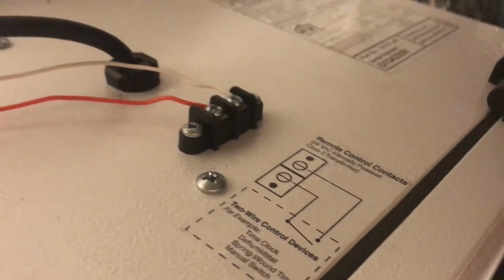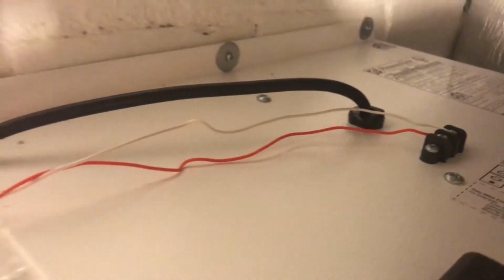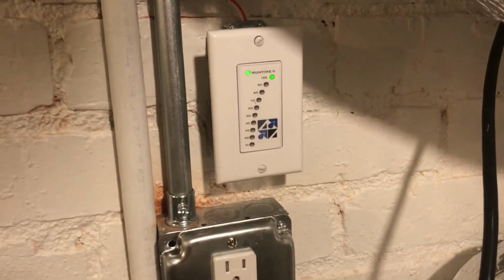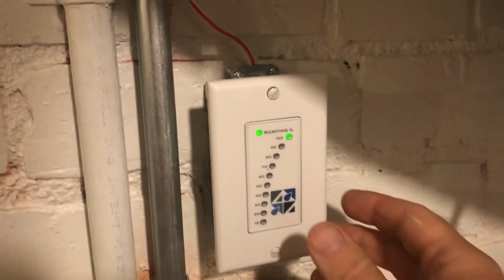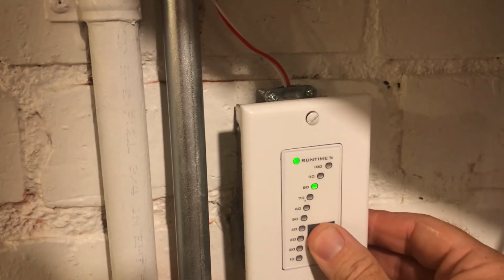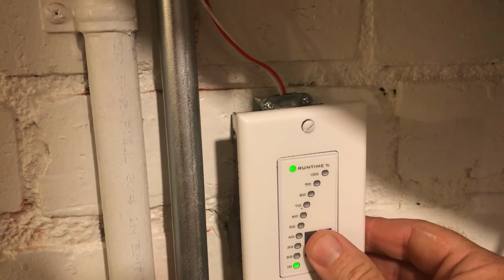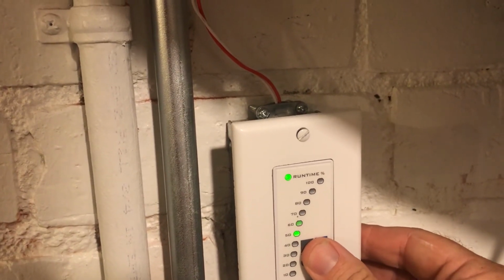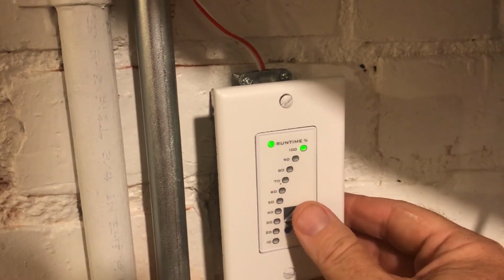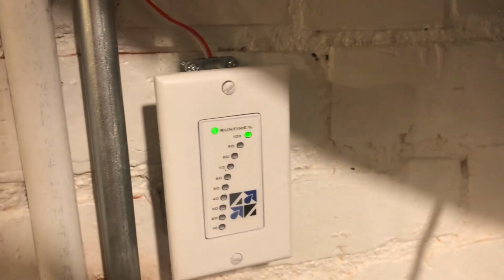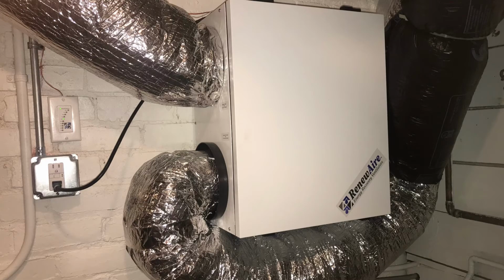The last step is ensuring that our electrical is connected using our thermostat wire from the unit. On this install, we just went ahead and mounted the PTL timer next to the unit, and then we can control the runtime. For a radon situation, we like to have it run 100% of the time, but the homeowner can adjust this based on their comfort level. And that's it. That's how we install the ERV for a self-vented installation.